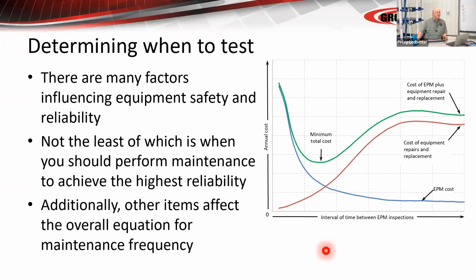When should you perform maintenance? Should you break it up and do it in sections and do a little bit every year? If it actually includes an inspection, that's probably a pretty smart thing. Going beyond 5 years, I can't recommend. Anything short of 5 years, I think you are doing yourself a favor. Beyond 5 years, at 5 years, lubrication issues begin to pop up, and 80 or 90% of the problems you're going to have in a shutdown are going to be insulation and lubrication.